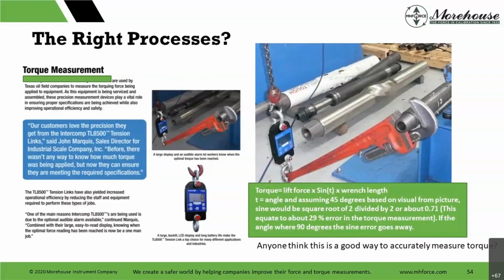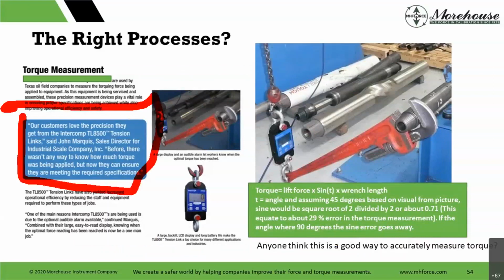This is TUR. Customer says, I probably need to gray out the customer. Customer says they love it. The company's giving an example here of torque. This is a great way to calibrate. Now I can put torque on my bar and I can know that I have the right amount of torque. Well, anybody that knows anything about torque knows it is lift force times sine. And if you look at this picture, my angle calculation may be off, but I'm saying that this is probably a 45 degree angle, maybe it's less, I don't know. I'm assuming 45 degrees. But what happens if we look at this picture? We get an error, just calculated error, assuming it's 45 degrees, of 29%. So the company here is promoting this as a way to measure torque. We don't know the true length either, but they're promoting this as a good way to measure torque.